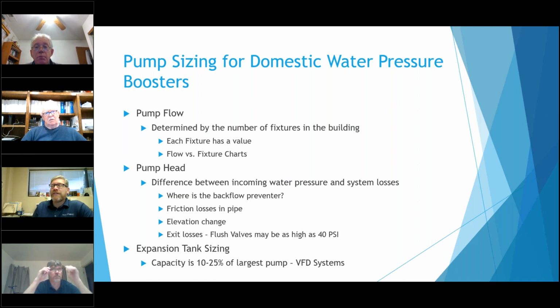So it's at 75 that we're looking at, and go to 10 to 25% of that. Most of the time you're looking at somewhere between a 7 to 20 gallon tank. So they're really fairly small. Like I said, it's just there for a buffer as you get some of these flush valves or solenoid valves that are closing, so that water has somewhere to go.